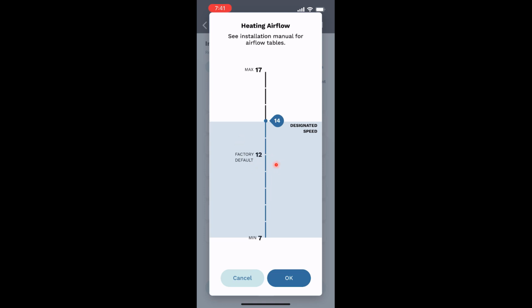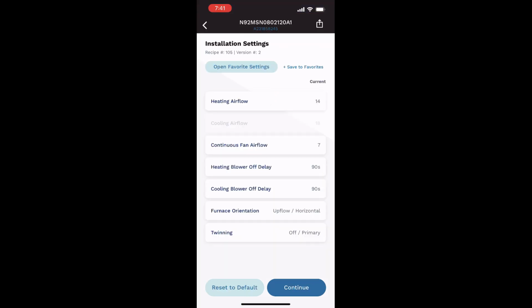The factory's at 12, but it'll let me slow it down to speed 7, depending on my CFM, my static pressure, and my heat, the heat rise and all that. That's all that's critical. And you can do all this by this setting here. Then you'll go back and let's do cooling.